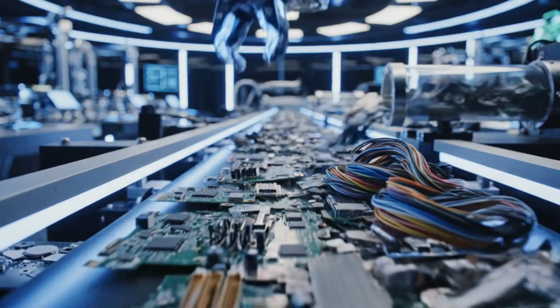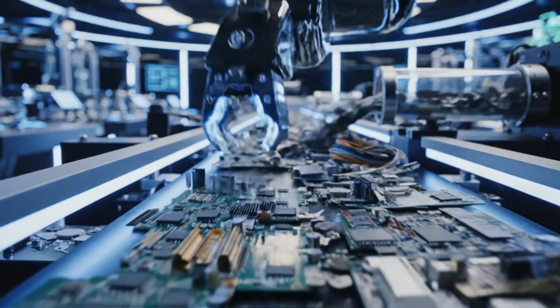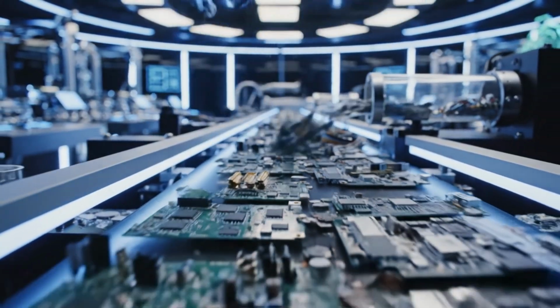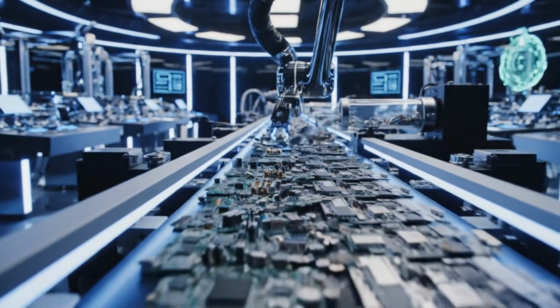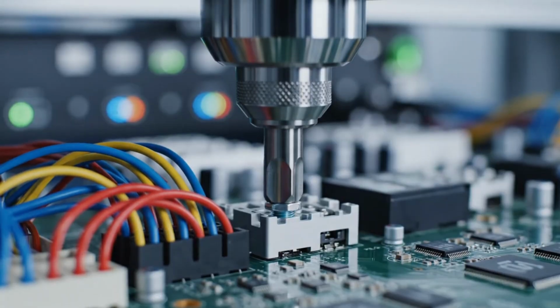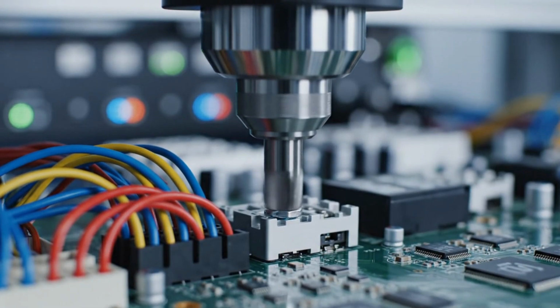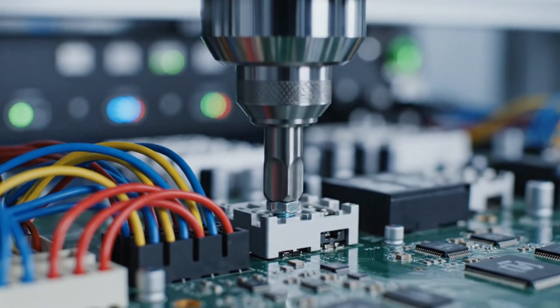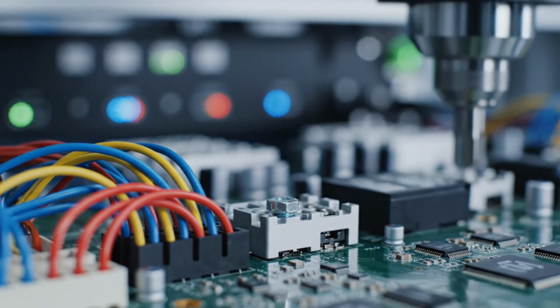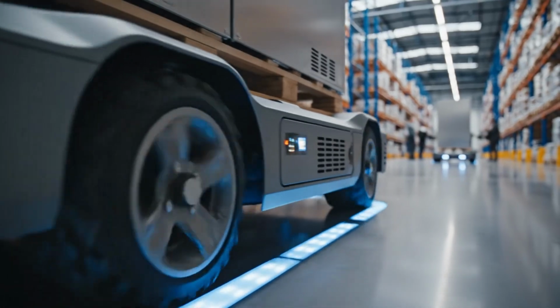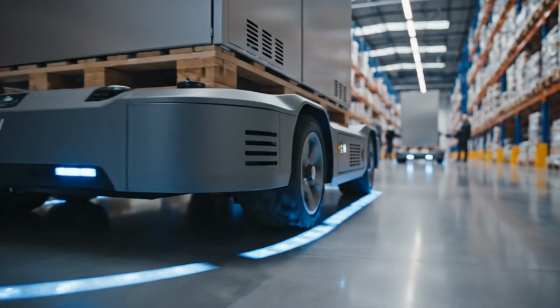Mechanical robustness is tested through vibration and shock simulations. Power equipment is mounted on multi-axis platforms that reproduce transport conditions and operational vibration profiles. These tests reveal micromovements, resonance effects, and mechanical fatigue risks that static inspection cannot detect.